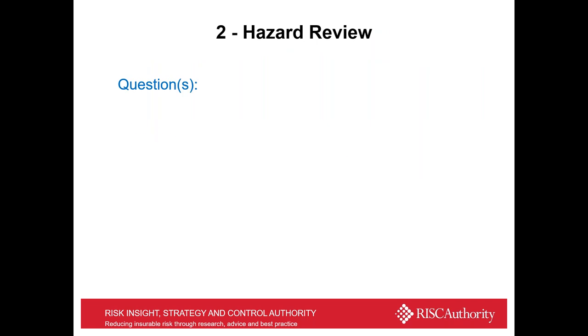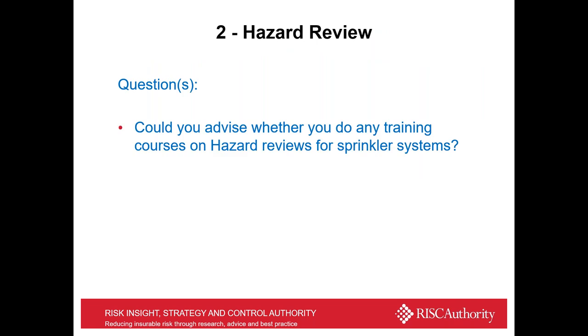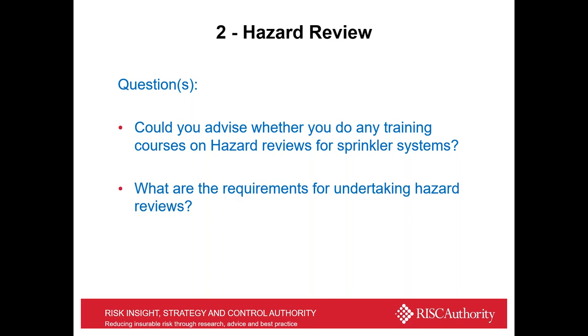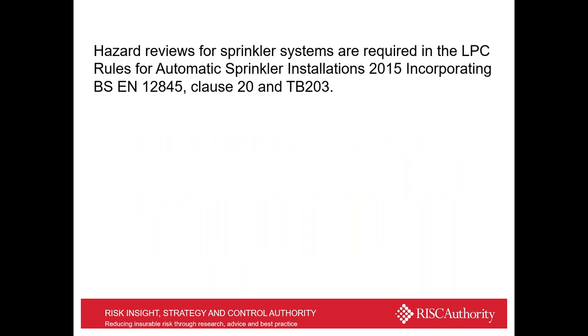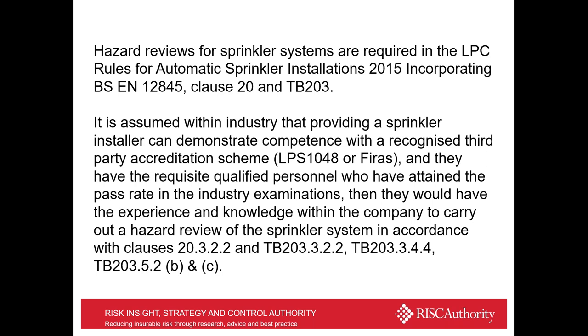Questions came in on hazard review: could you advise on training courses on hazard review for sprinkler systems? What are the requirements for undertaking hazard reviews? Who should carry out hazard reviews? Hazard reviews for sprinkler systems are required in the LPC rules Clause 20 and are covered in technical bulletin TB203. Within the industry it is assumed that providing a sprinkler installer can demonstrate competence with a recognized third-party accreditation scheme — LPS 1048, FIRAC, or IFC — and they have requisite qualified personnel who attain the pass rate in the industry examinations, then they would have the experience and knowledge to carry out a hazard review.